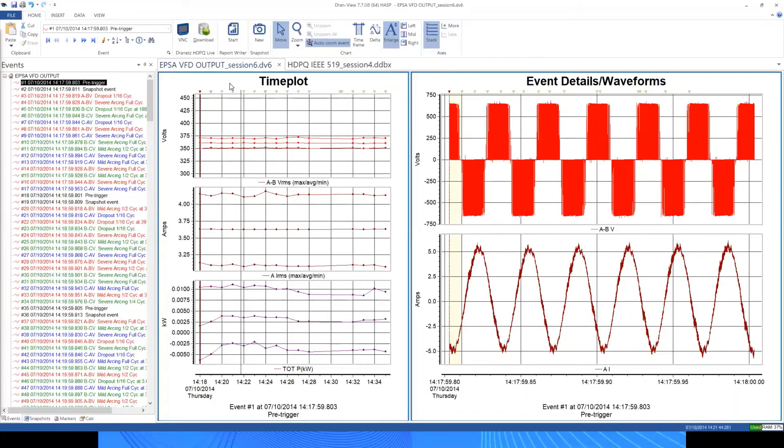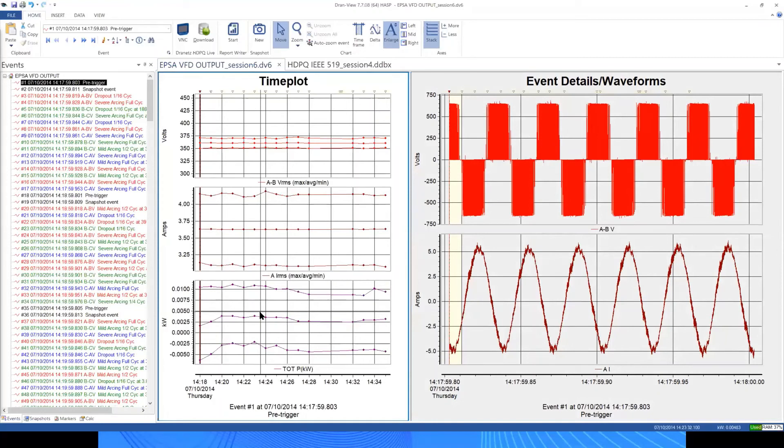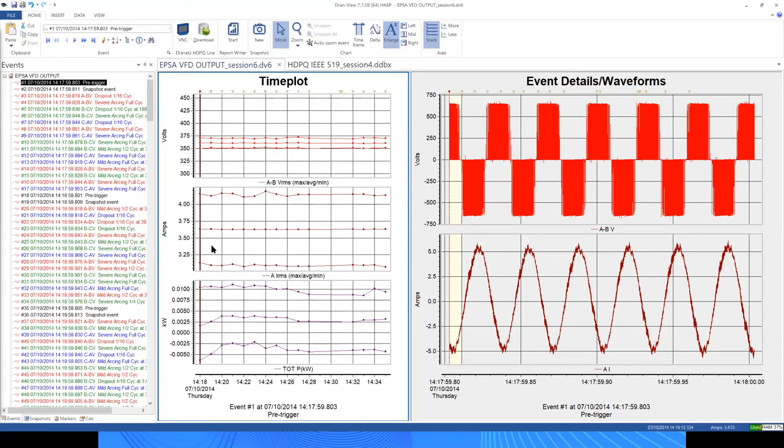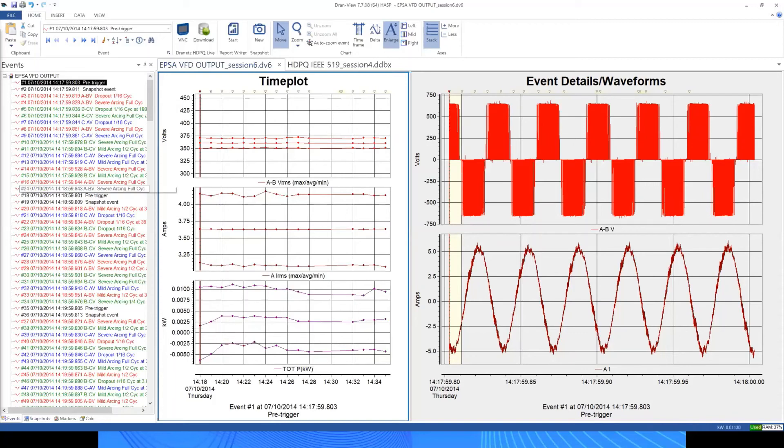You can look and see our regular event list here. Here's our timeline trend. William had a question before about can the power be done - yes, this is just a quick power trend here. This is a very short motor test that was done, so there's not much time duration. But what I have here is the voltage, the current and the total kilowatts. It's a low power motor - this is just an offline test or simulated test. But yes, William, you can get your power information. Let me pause and let's look at the chats here, and then we'll wrap up this particular set.